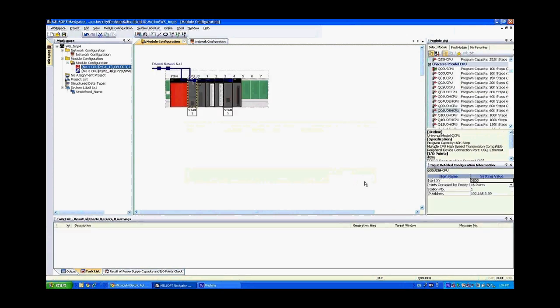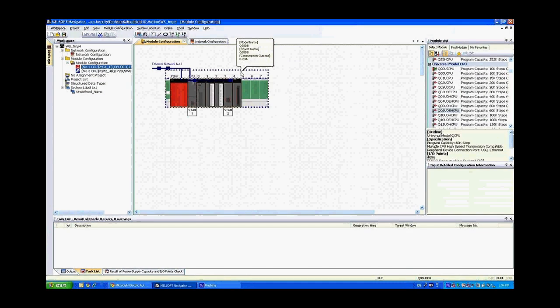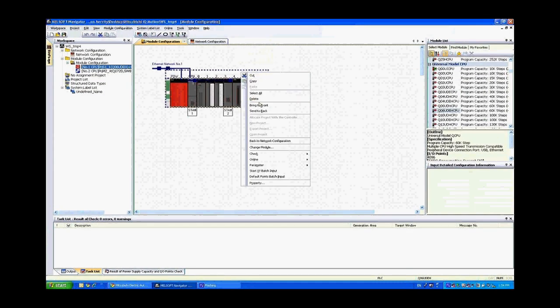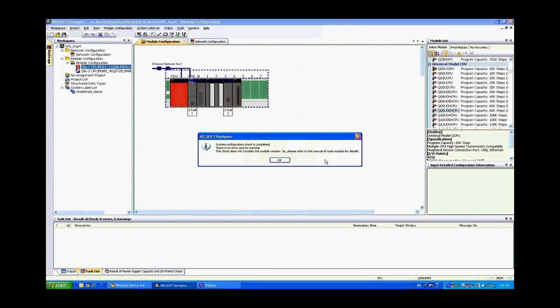Now you'll see that station number is 1 and if I click on the ethernet module you'll also see that station number is 1. We're going to want to change the ethernet module so that that's station number 2 so that again there's no conflict. Now if I right click on the back plane again and do a check for system configuration there's no error and no warning.